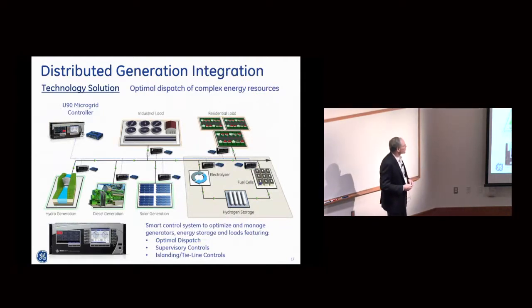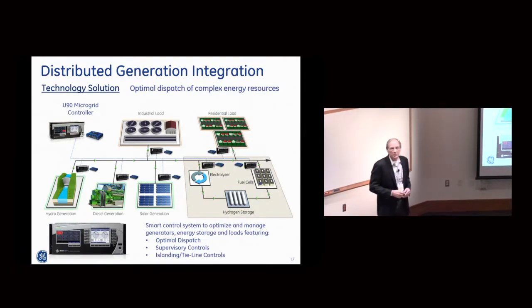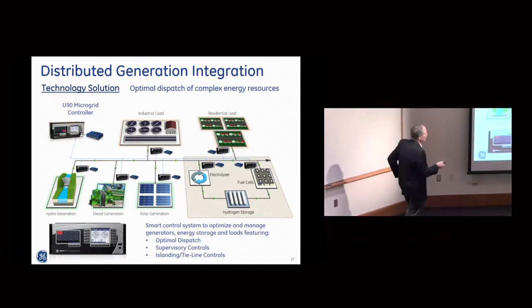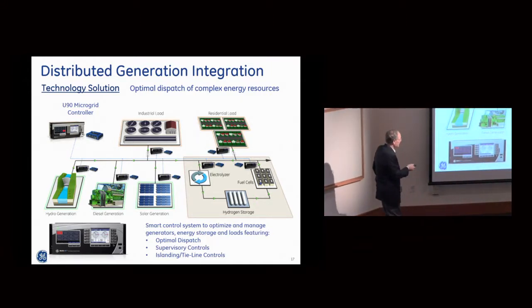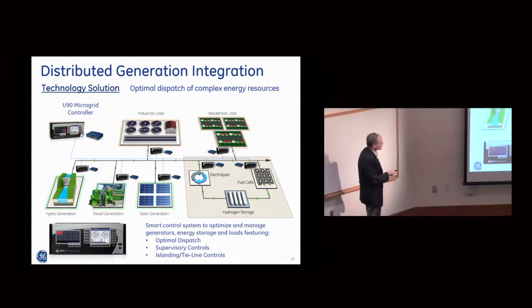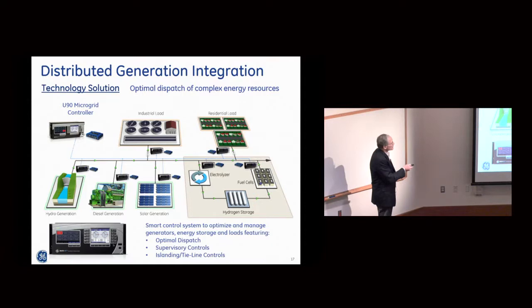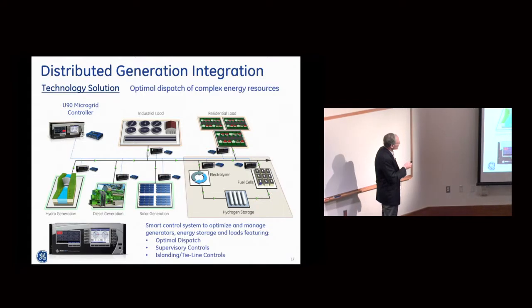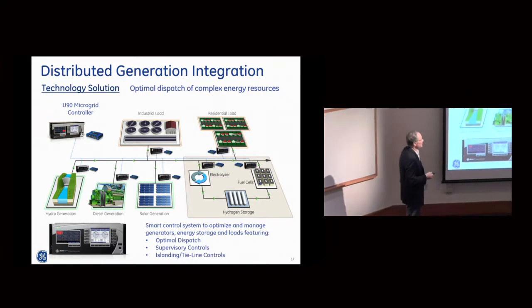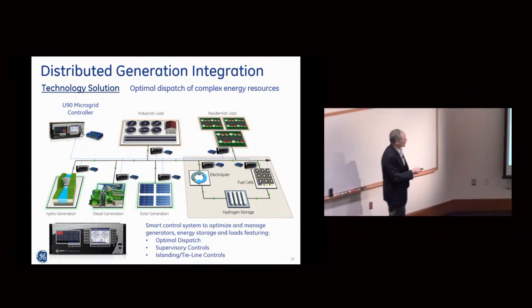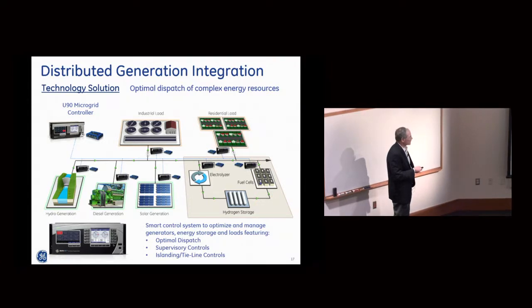This is the first microgrid project we did at GE, at a rural village in British Columbia that had fuel cells, PV panels, low-head hydro, traditional diesel, and both industrial and residential load. We took a relay and added logic to it to act as a microgrid controller, to make sure the load was satisfied on a continuous basis while optimizing the use of the fuel cells, the PV panels, and the hydro, and minimizing the use of diesel, with high-speed communications. Each of these blue boxes represents communications tying everything together.